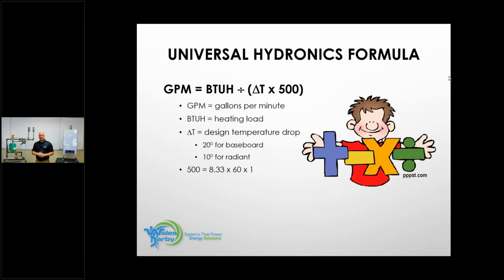That's what's taking place. So to go further with this formula here, GPM equals BTU divided by delta T times 500. If we want to use this formula, and I have 10,000 right there above my delta T and 500 sign, and I tell you that this is a 100,000 BTU boiler, please do the math. 20 times 500 is 10,000. 10,000 divided into your boiler size, 100,000 BTU, and send Jim the answer. What is your gallon per minute flow rate required to support this 100,000 BTU boiler at a 20-degree delta T?